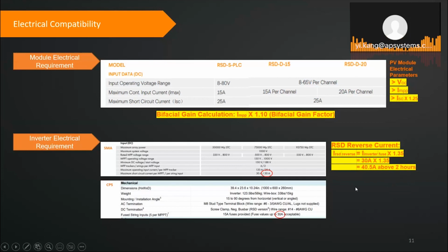On this side, just so you know, our reverse current could go up to 40.5 amp, like I said before, for about 2 hours. That's exactly the same as the string inverter standard requirement.